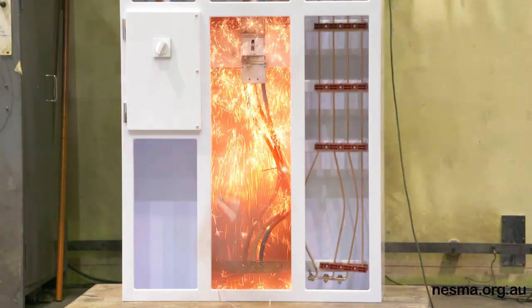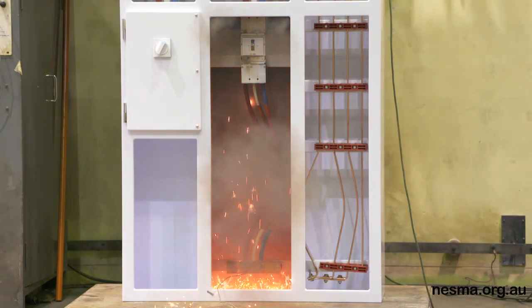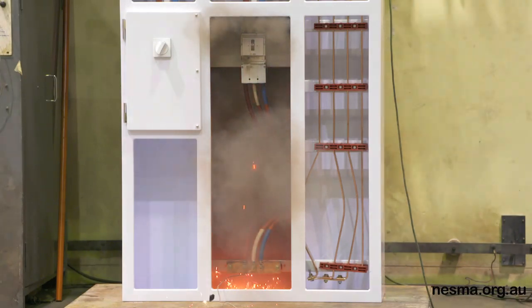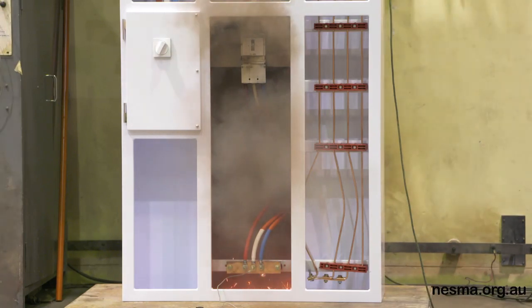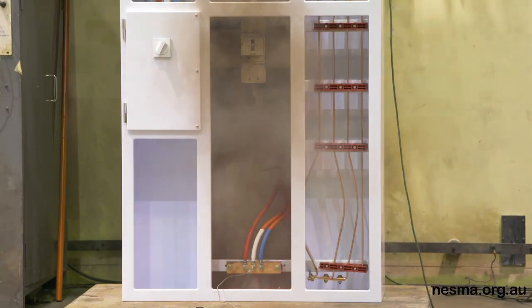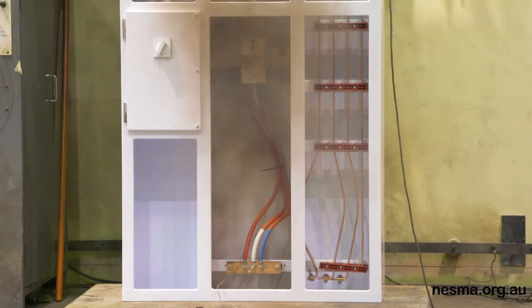And so the circuit breaker has operated. You've seen the toggle move to the trip position. You just see that bit of black insulation falling out now and bouncing on the trolley. That was one of the barriers or vents that's at the line side pole terminal. It just goes into the barrier that's on the top to stop inadvertent contact with the terminals.